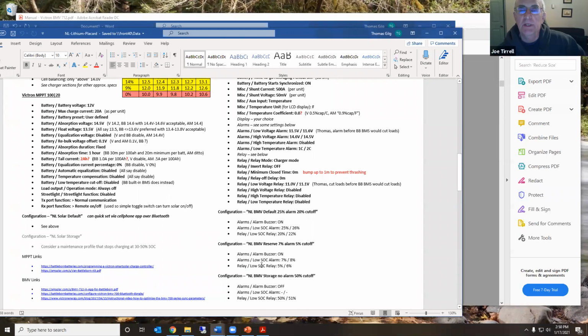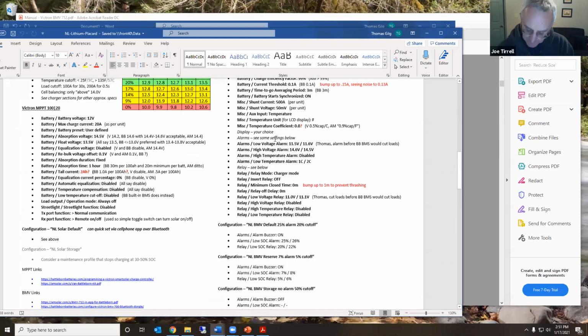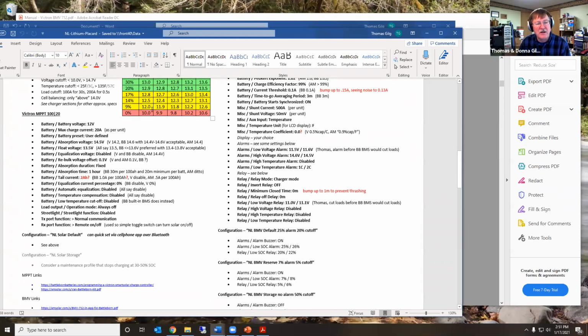But okay, so if I'm looking at your list, you have an 11.5 and an 11.0. If you go up to see some settings below, the first value you have is 11.5. Oh, the 11.5 is apparently when I sound the alarm. Okay, and it seemed pretty reasonable on the voltage chart that if you're at 11.5 volts, you're below 9%, probably down like 5% of your battery left. And then the 11 volts was, let's go ahead and formally throw the relay and cut the loads.